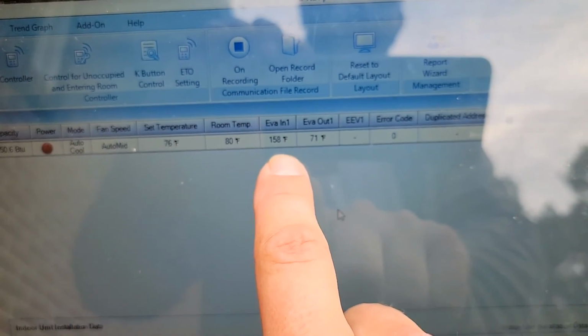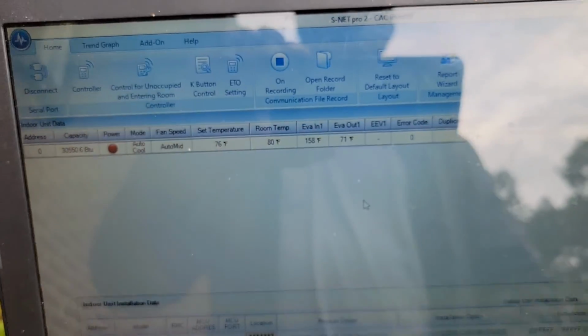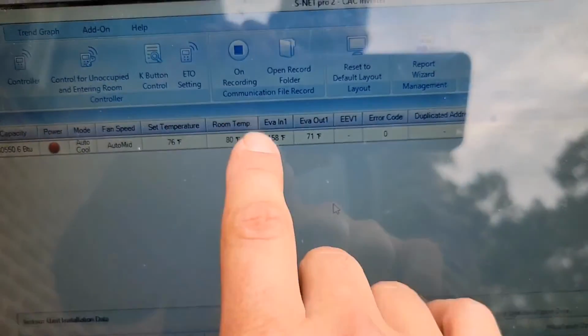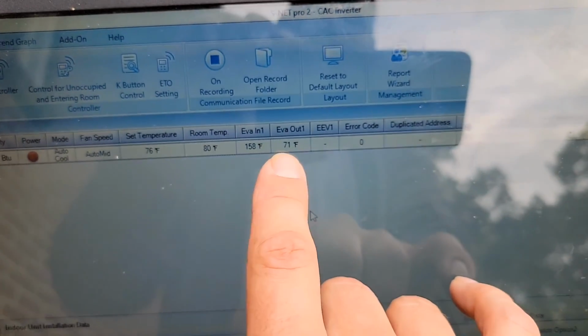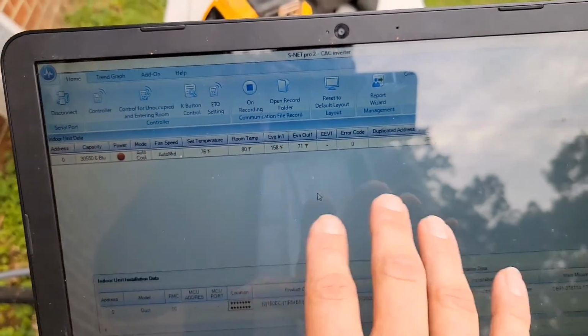I don't even have to go inside and check the sensors. Look, evaporator inlet, 158 degrees. I think not, that's way off. Evaporator inlet should be just about the same as the evaporator outlet, especially with the unit not running and hasn't been running.